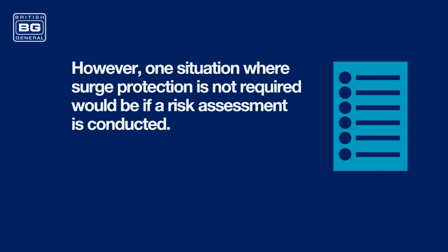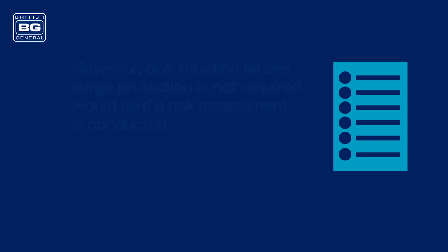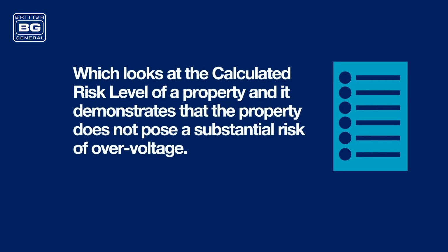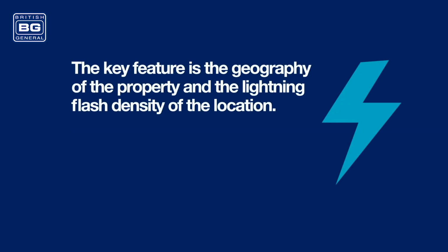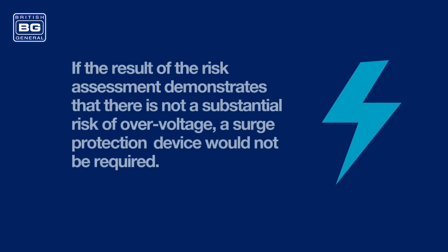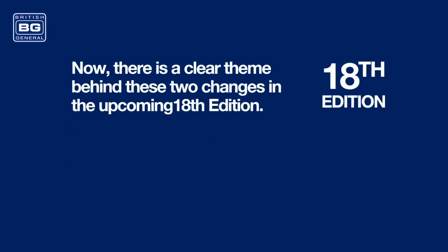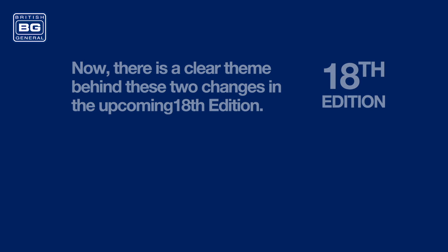However, one situation where surge protection is not required would be if a risk assessment is conducted, which looks at the calculated risk level of a property, and it demonstrates that the property does not pose a substantial risk of overvoltage. The key feature is the geography of the property and the lightning flash density of the location. If the result of the risk assessment demonstrates that there is no substantial risk of overvoltage, a surge protection device would not be required. Now, there is a clear theme behind these two changes in the upcoming 18th edition.